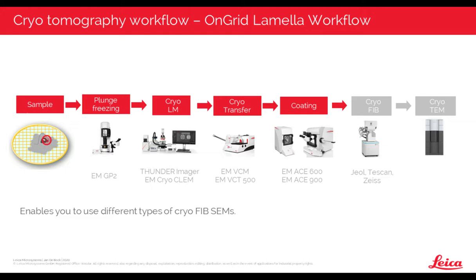What does the Thunder processing actually do? The heart of it is computational clearing: it detects and removes the out-of-focus background light for each image, making the signal of interest directly accessible. At the same time, in the in-focus area, the edges of the signal and the intensity of the specimen's features remain intact. This is important — it's not simply a background subtraction where you lose all signal; the features of your sample are kept intact. That's why you can select the expected feature size for the processing.